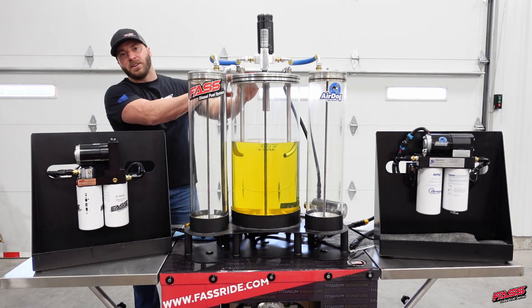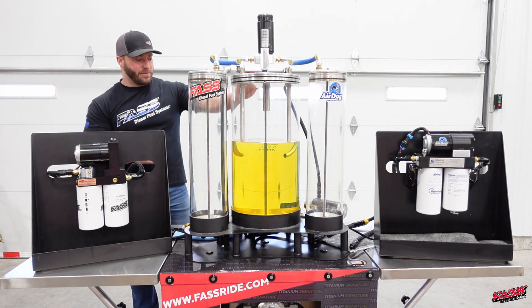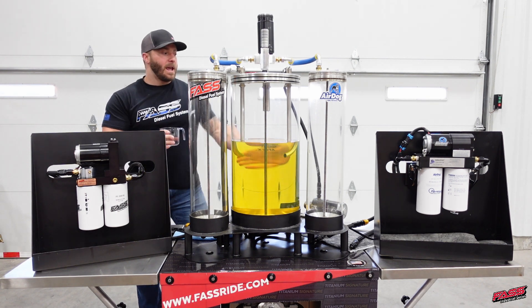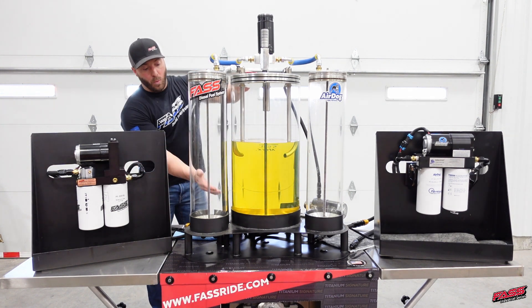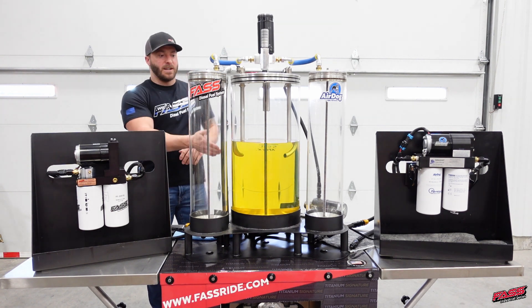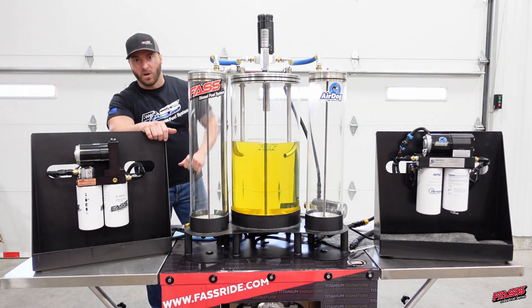The center cylinder here is just filled with number two diesel fuel right out of the pump here in Marthasville, Missouri. We're going to be putting in some water, kicking on a standalone fuel pump that we have on here. What that's going to do is turn the water from free water at the bottom to emulsified water where it blends in with the fuel and becomes very cloudy. That's actually more difficult to separate out of the fuel than free water.